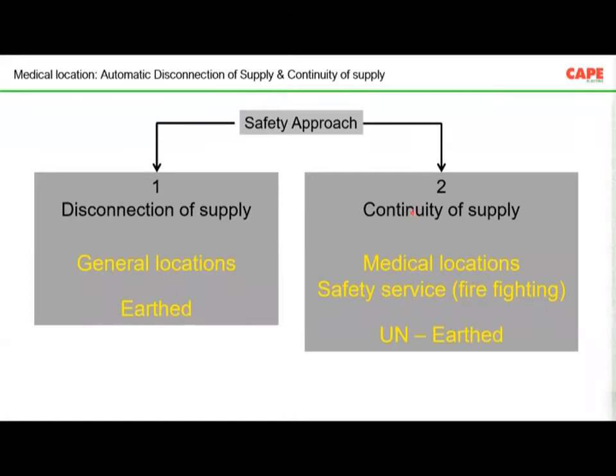The application number 2, continuity of supply. What does it mean? In a hospital, especially in a group 2 medical location where operations happen or the patient is connected to various biomedical equipment. Imagine you are putting a new device into the circuit which is faulty. Without knowing the problem, you have put the device into the circuit and the MCB tripped. So if disconnection happens in that kind of an area, the patient will be in danger because the supply itself has been disconnected. For that application, especially in a group 2 medical location, continuity of supply is important.